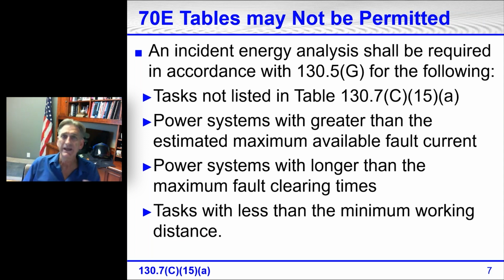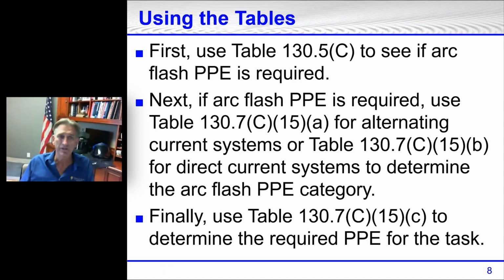Also, in using the tables, we have to look for the task that we're going to be doing in front of live electrical or potentially live electrical equipment. If the task is not listed, then we can't use the table. We would have to have an arc flash analysis performed on the equipment. So first, use table 130.5C to see if arc flash PPE is required. This first table will tell us whether we need arc rated PPE. If so, we'll go to the next table and the next. Next, if arc flash PPE is required, use table 130.7C15A for alternating current systems, or table 130.7C15B for direct current systems, to determine the arc flash PPE category. Finally, use table 130.7C15C to determine the required PPE for the task.